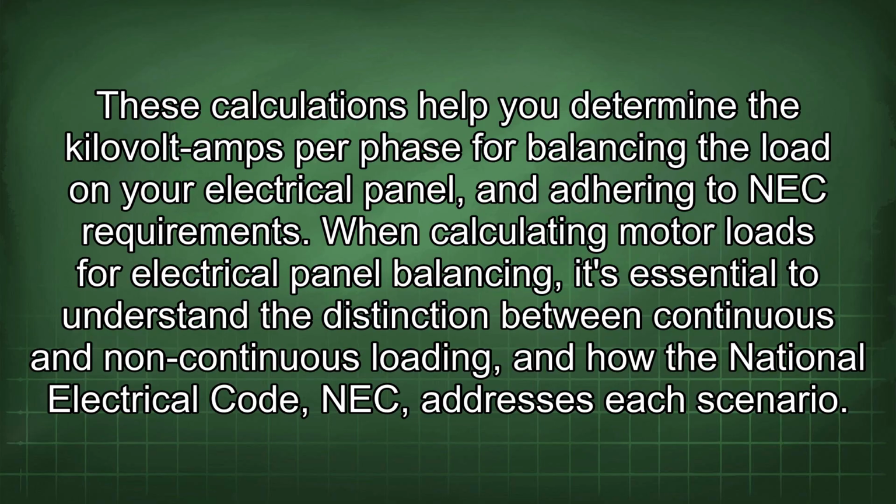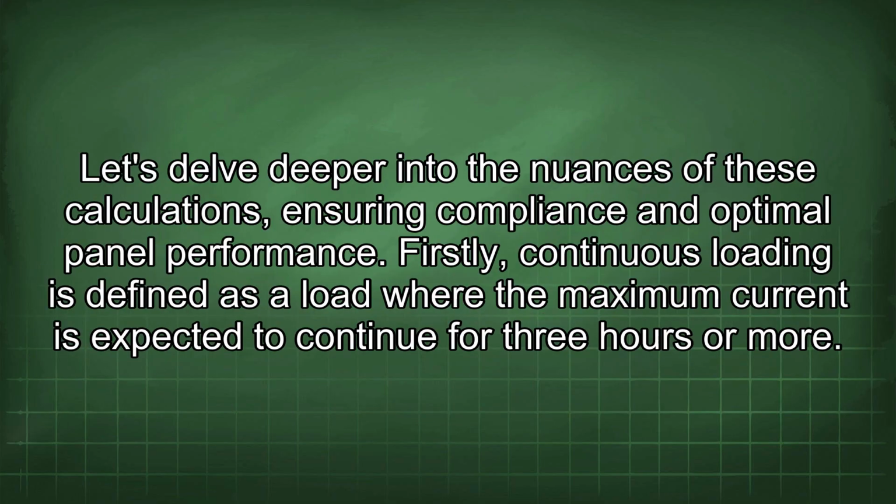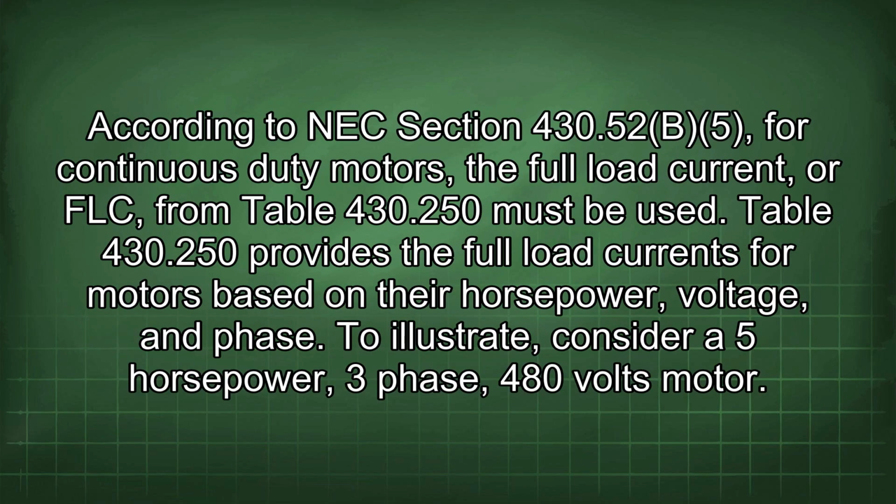to NEC requirements. When calculating motor loads for electrical panel balancing, it's essential to understand the distinction between continuous and non-continuous loading and how the National Electrical Code, NEC, addresses each scenario. Let's delve deeper into the nuances of these calculations, ensuring compliance and optimal panel performance. Firstly, continuous loading is defined as a load where the maximum current is expected to continue for 3 hours or more.